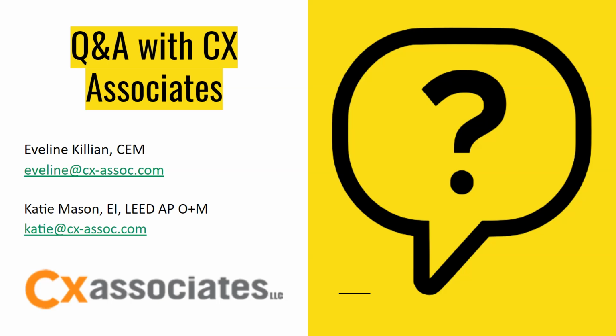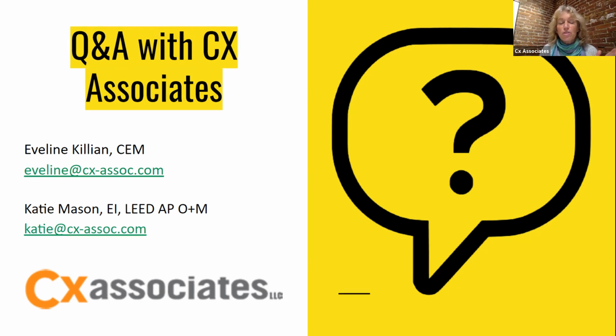Our first question is, what kind of ongoing costs could occur after updating ventilation, aside from the unit cost? What other costs could be included? Yeah, that's a good question. So the air handling unit, if you have one, might have just ever so slightly increase, but really just a very small amount, because you're bringing in potentially more air. So a small amount of electric increase for the fan, and then, again, depending on how much ventilation air you're bringing in, you might have a small increase in natural gas for your heating, if you're heating that outside air.